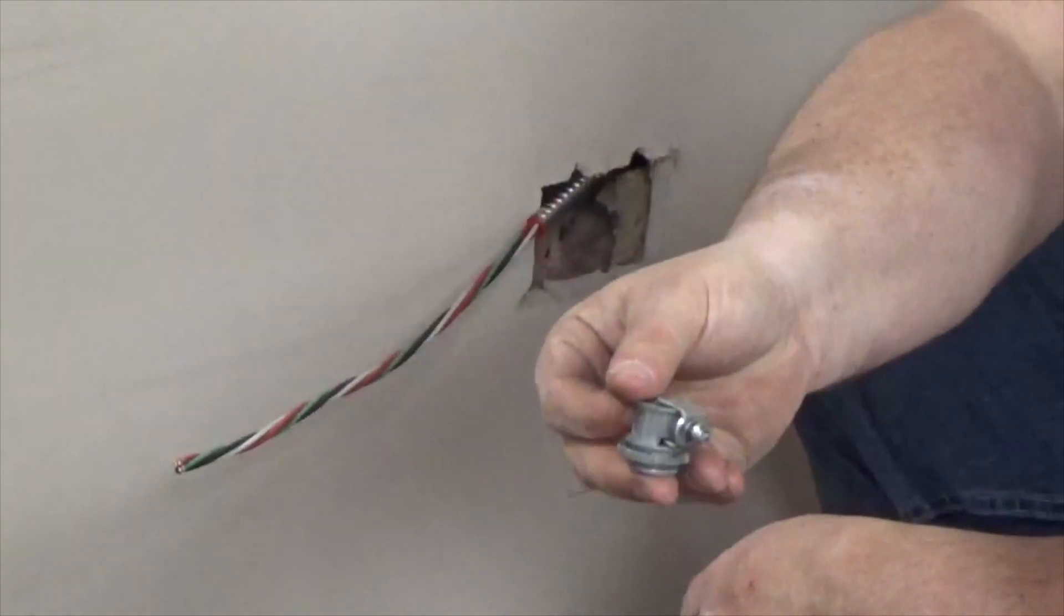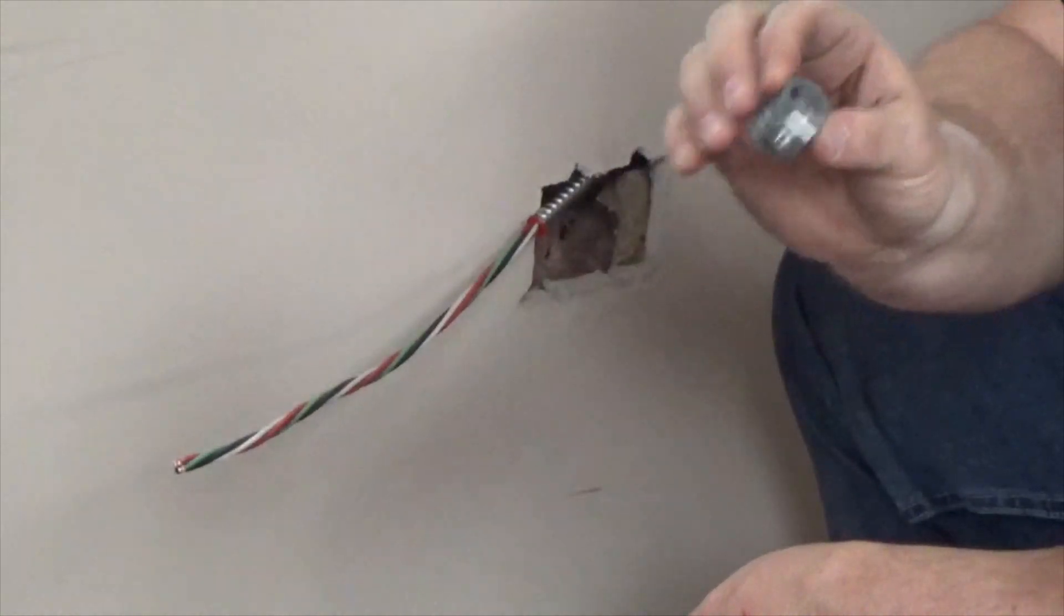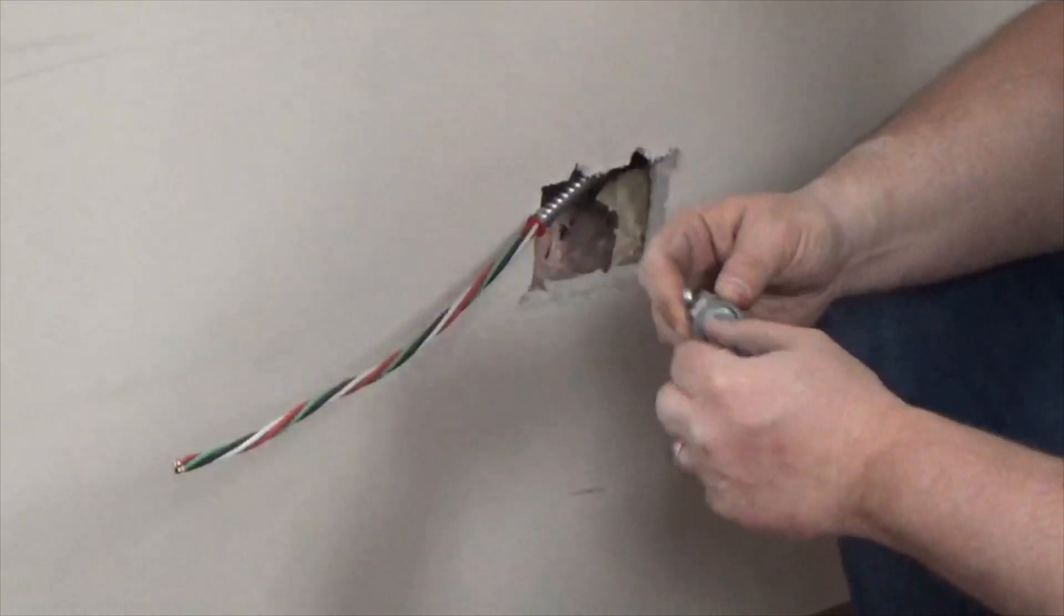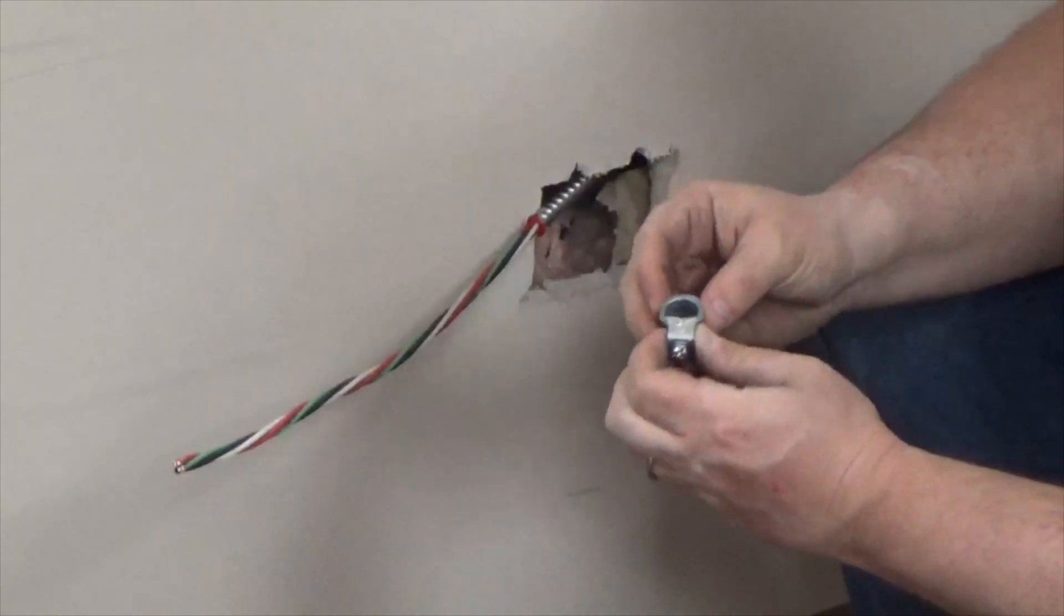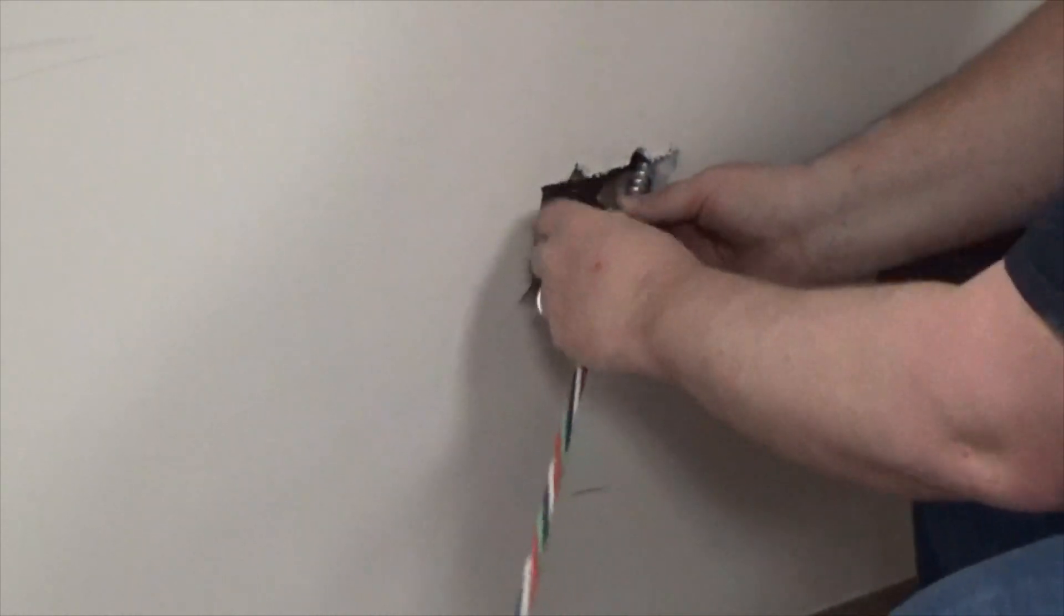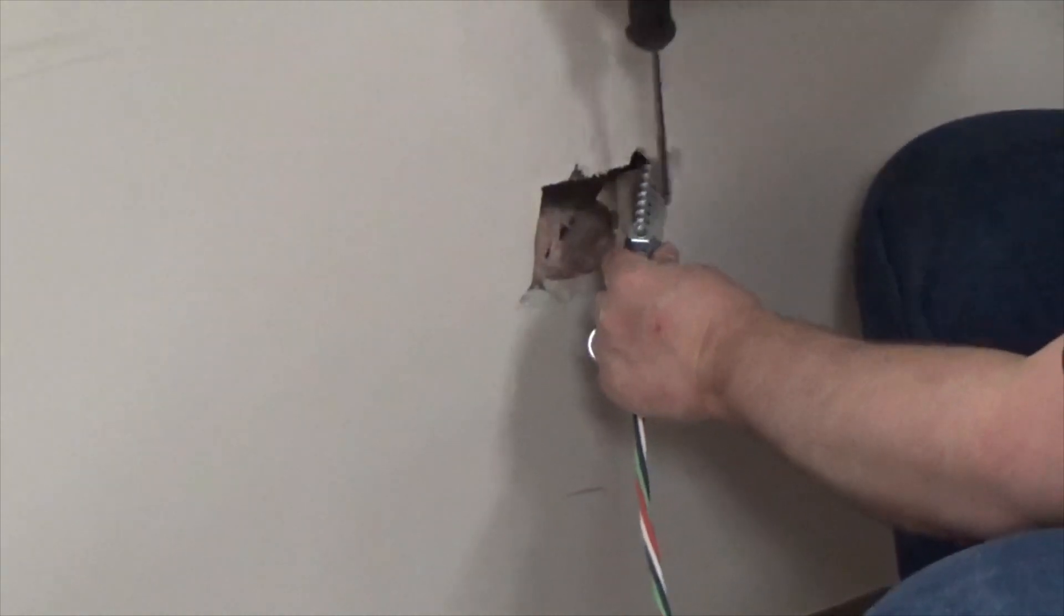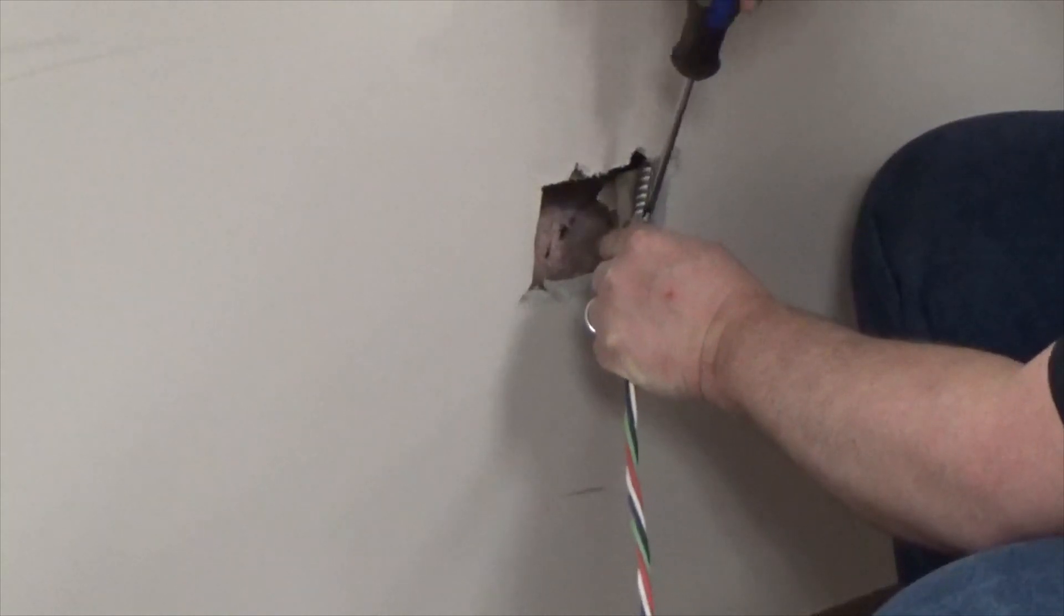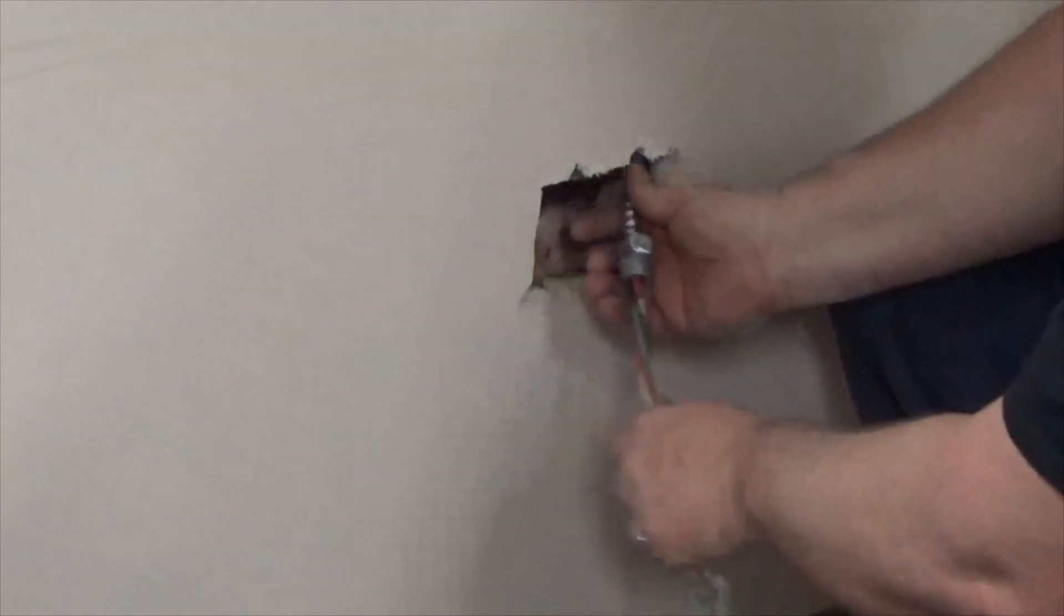So, I have a single MC connector. You want to make sure it's an MC connector, not a Romex connector. Make sure you look at the packaging and make sure that you understand exactly what type of connector you're using for what wire you're using. We're going to remove the lock nut. We're going to loosen up here, slide it in, and then we're going to tighten it down. I'm going to make sure it doesn't come off.